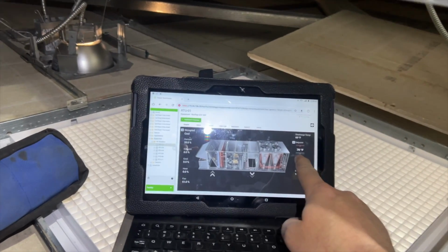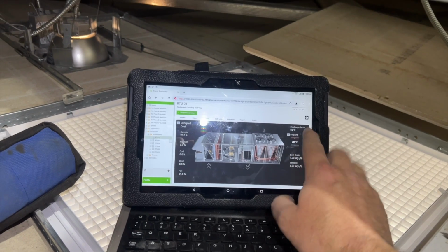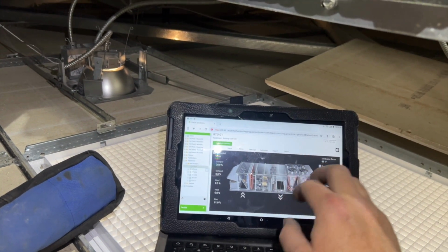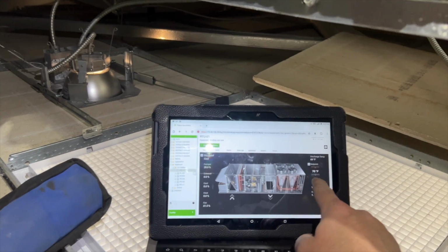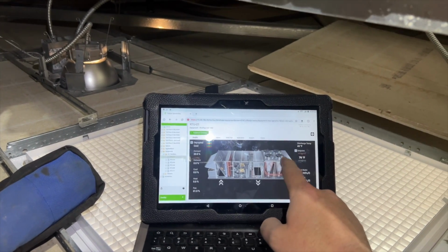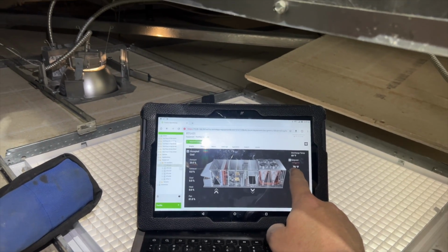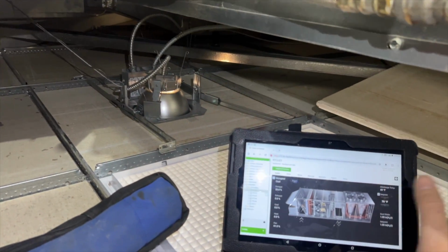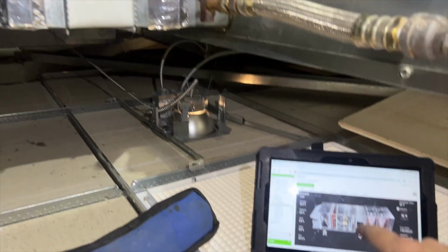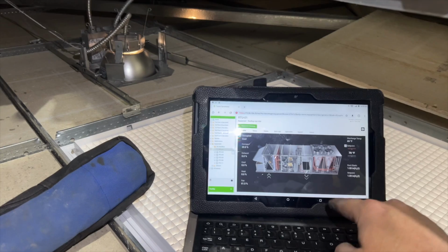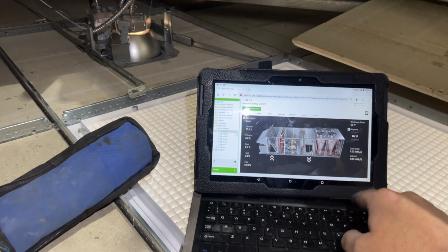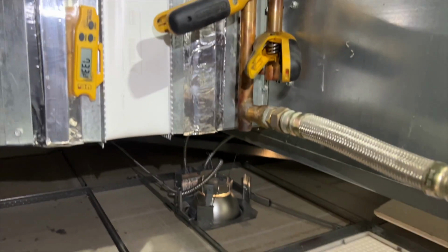The issue here is this set point. So apparently it's not set like that. The system will actually determine based on all the zones, so it'll average out all of the zones and then change this periodically through the day. So I think there's a programming issue. The set point's too high. We were watching this remotely yesterday, and this was set to like 73 degree air. So if you're trying to cool a space down to like 60 something and you have 73 degree discharge or supply air, it's just not gonna cool the space. So we're gonna have to go in there and reprogram something. Well, not us, but you know, Trane or whoever handles that. But I think there's a programming issue or some kind of set point issue with the RTU, just the supply is not cold enough.